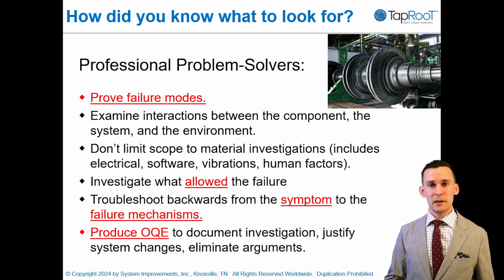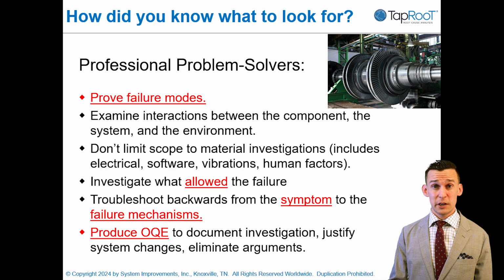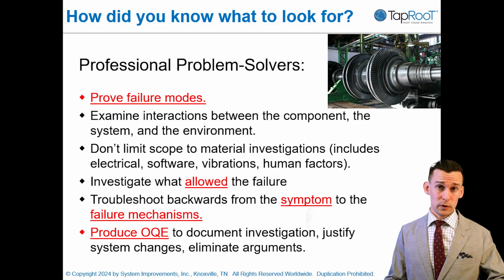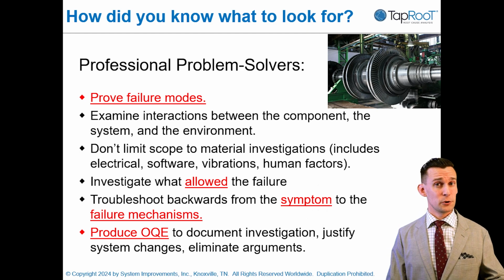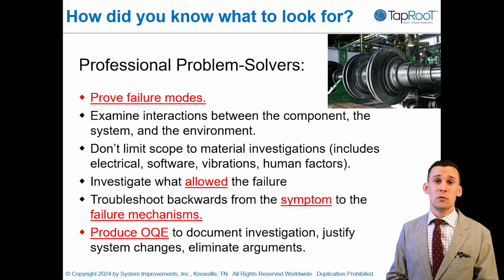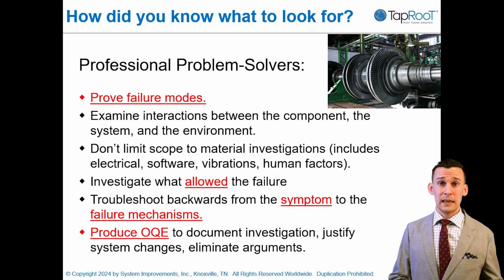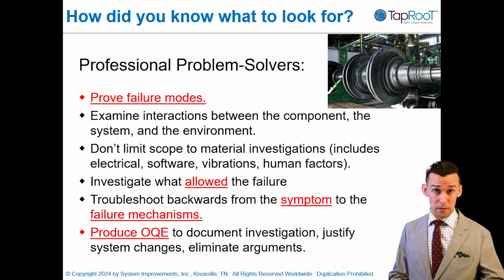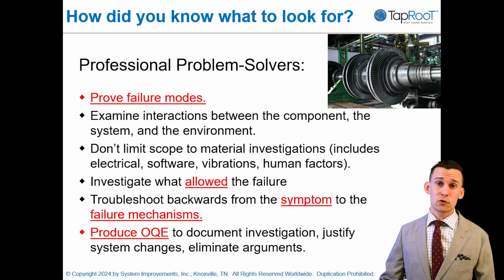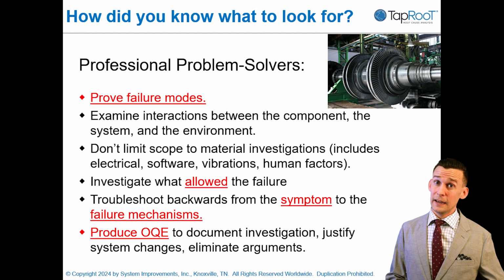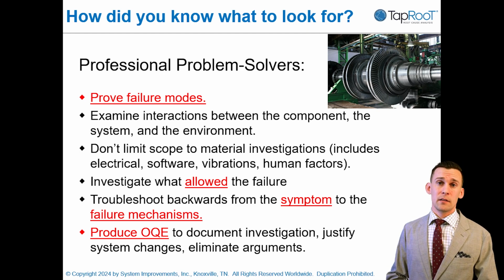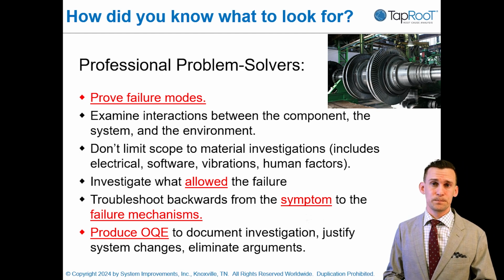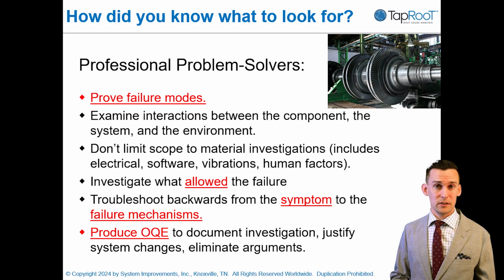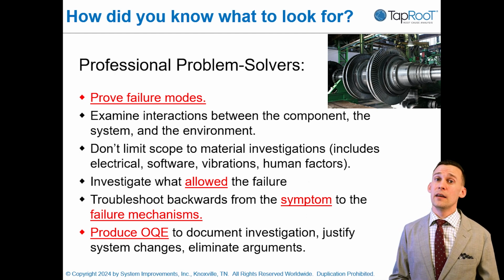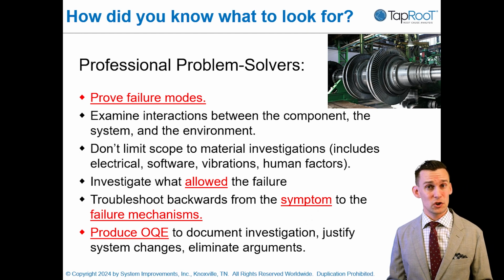And don't just limit your investigation to material aspects - doing chemical swipes, metallurgy, lubrication analysis. We need to look at everything that pump may be connected to: its electric power supply to the motor, any electronic controls, any sensors, the piping it's connected to, and obviously the humans operating it, maintaining it, and that installed it.